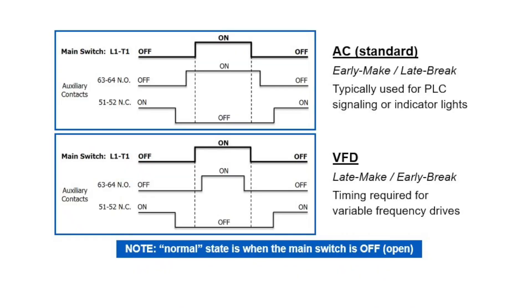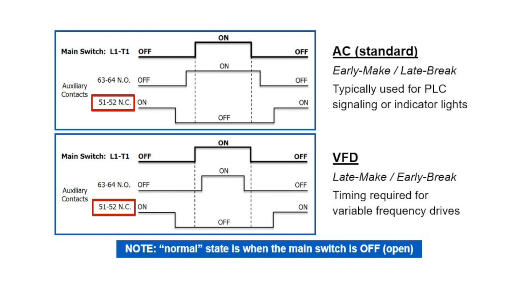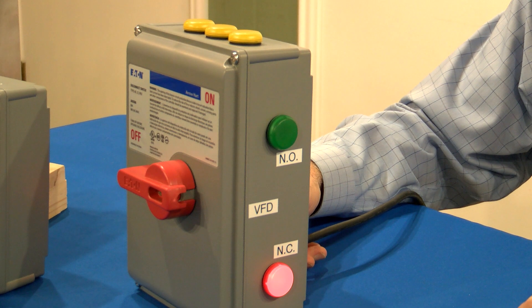Finally, let's talk about auxiliary contacts. Here's a timing chart showing how these interact with the main switch. Auxiliary contacts provide a way to send a signal to another device based on the state of the main switch contacts — open, which is off, or closed, which is on. The auxiliaries can be normally open or normally closed. Note that the normal state is when the main switch is off.